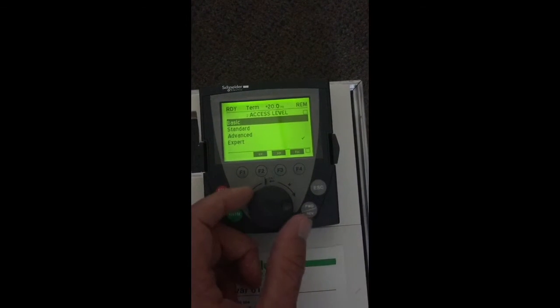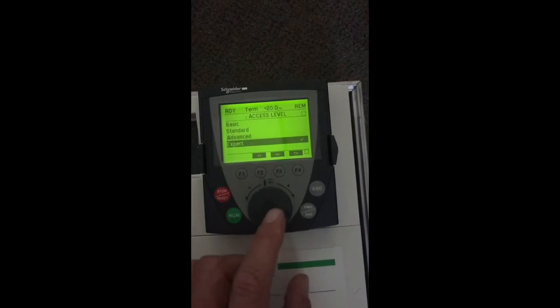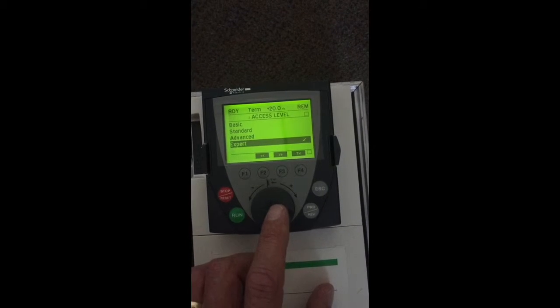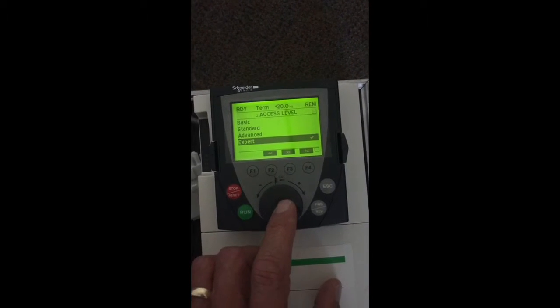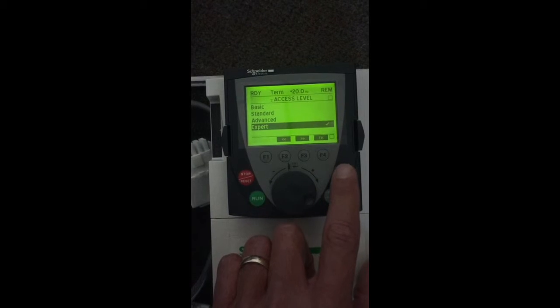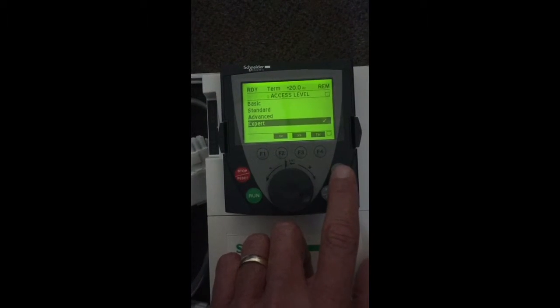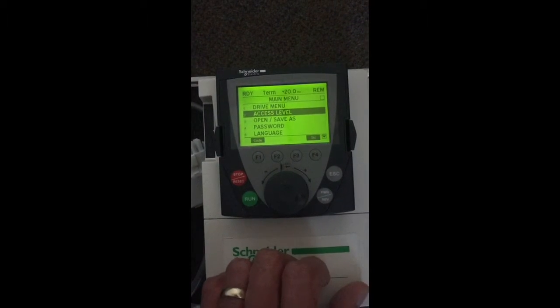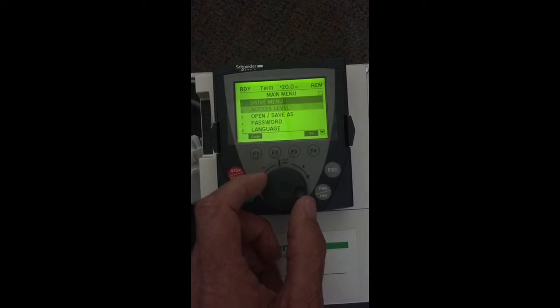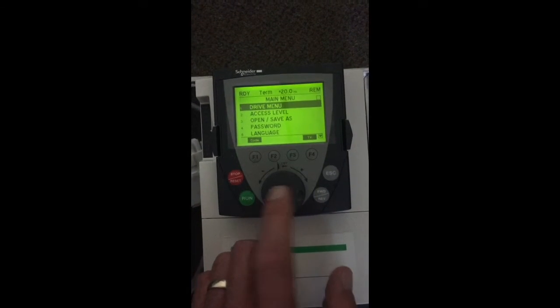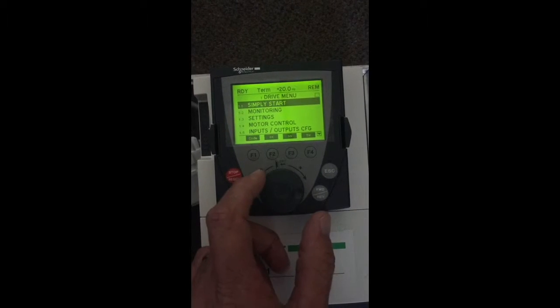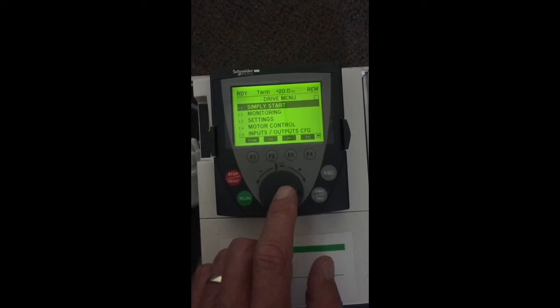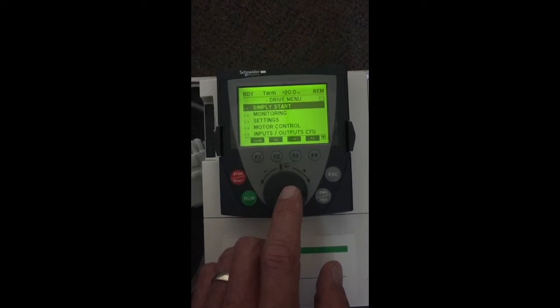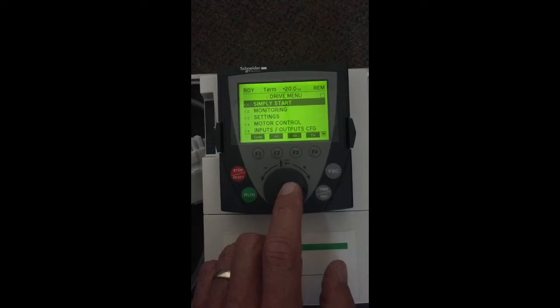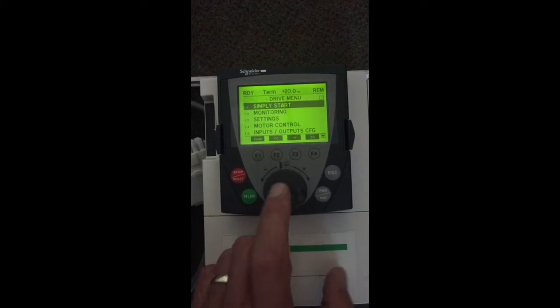Set your access level to expert, and you'll see that the check mark is beside the expert level. Escape back out. Go into drive menu by rotating the dial, pressing the enter button. Simply start will allow you to enter your motor parameters for your drive. To enter into this menu, press the button.